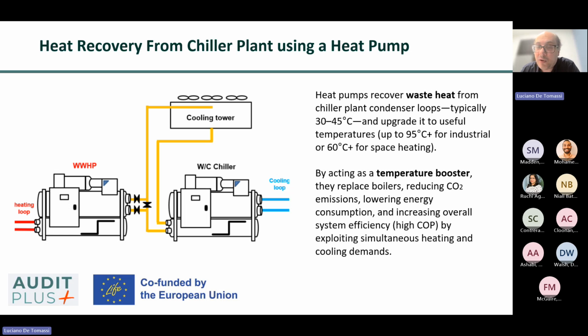In this configuration, the cooling process effectively provides the free heat source, and the heat pump only supplies the additional energy needed to raise the temperature. This results in a high overall coefficient of performance, often significantly higher than standalone heating systems, because the system benefits from heat that would otherwise be wasted.